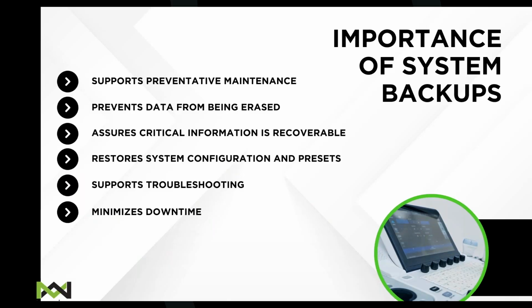Some of the importance is to make sure you're preserving configuration and presets. All ultrasound systems are customized with site-specific presets, measurements, and workflow preferences. Backups ensure that these settings can be quickly restored if the system crashes, undergoes repair, or requires some type of software reload. Like I said, when I get calls for tech support, that's one of the first things I ask, if the system has a backup. A lot of times when you go out on a service call, you'll find that the backup could be 2 to 3 years old. So if any changes have been made to the system between that time, they won't be recorded, obviously.